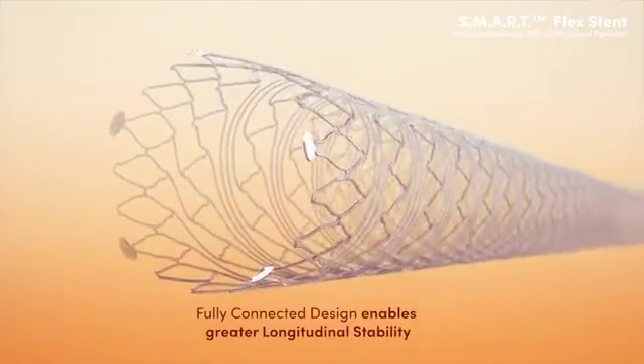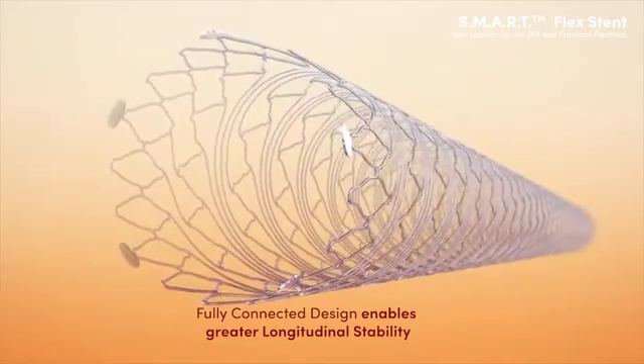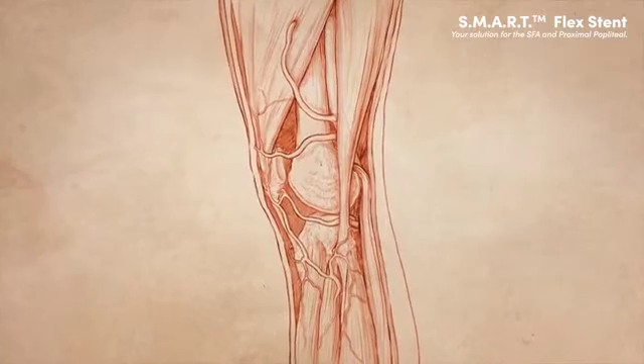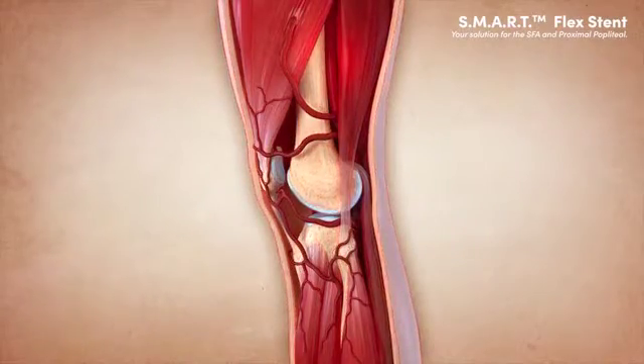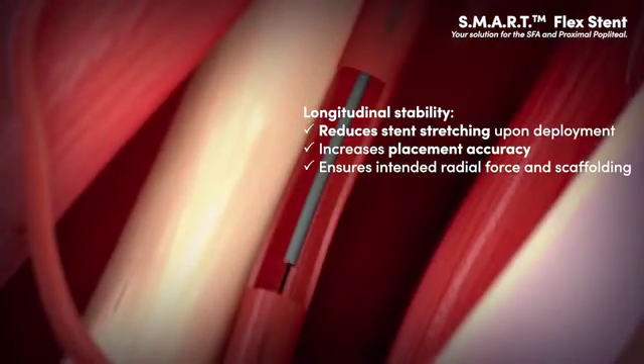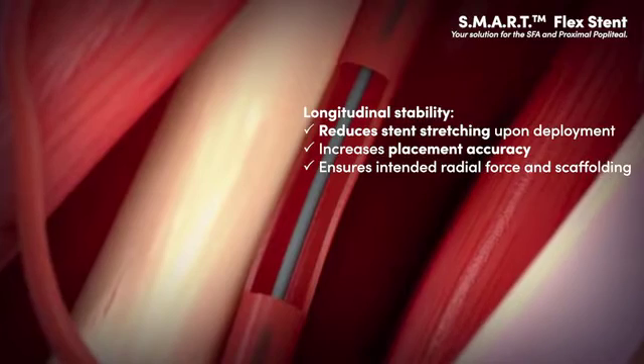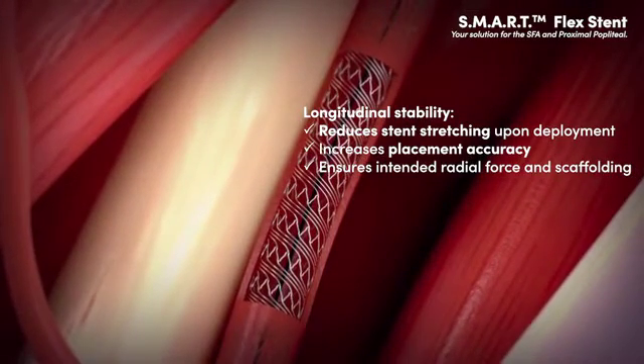The fully connected design of the S.M.A.R.T. Flex stent provides greater longitudinal stability. Greater longitudinal stability helps reduce stent stretching upon deployment. It increases placement accuracy and ensures the stent achieves its intended radial force and scaffolding.